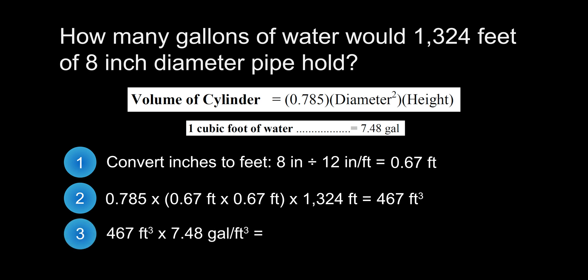In the final step, we will take the volume of the pipe, which was 467 cubic feet, and multiply it by the conversion factor of 7.48 gallons per cubic foot, yielding our final answer of 3,493 gallons.